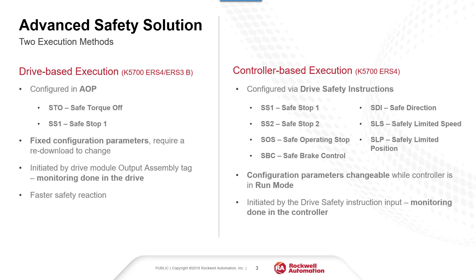The configured parameters of the drive safety instruction are changeable while the controller is in run mode for added flexibility. Execution of a controller-based safety function is initiated via the drive safety instruction's input operand. Once initiated, the monitoring is done in the controller by the drive safety instruction.